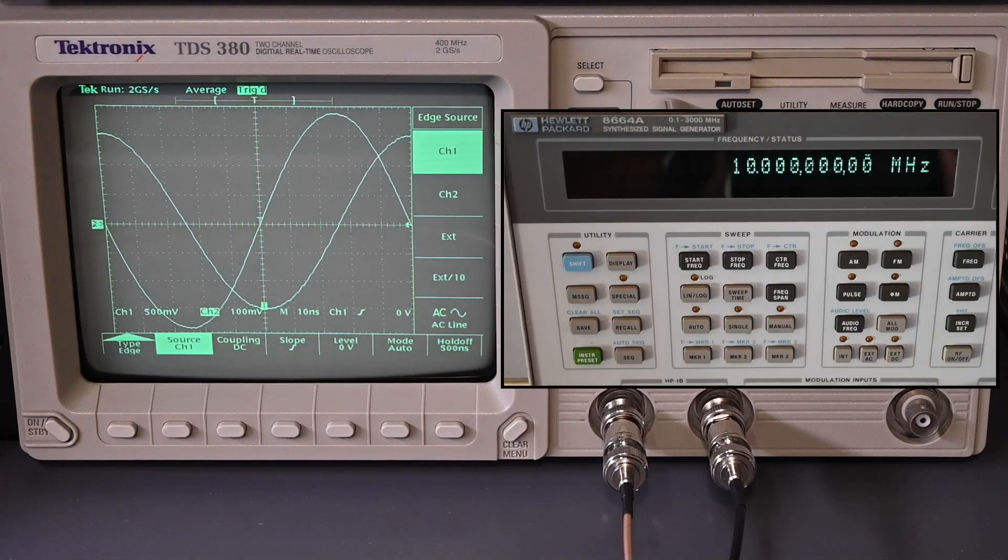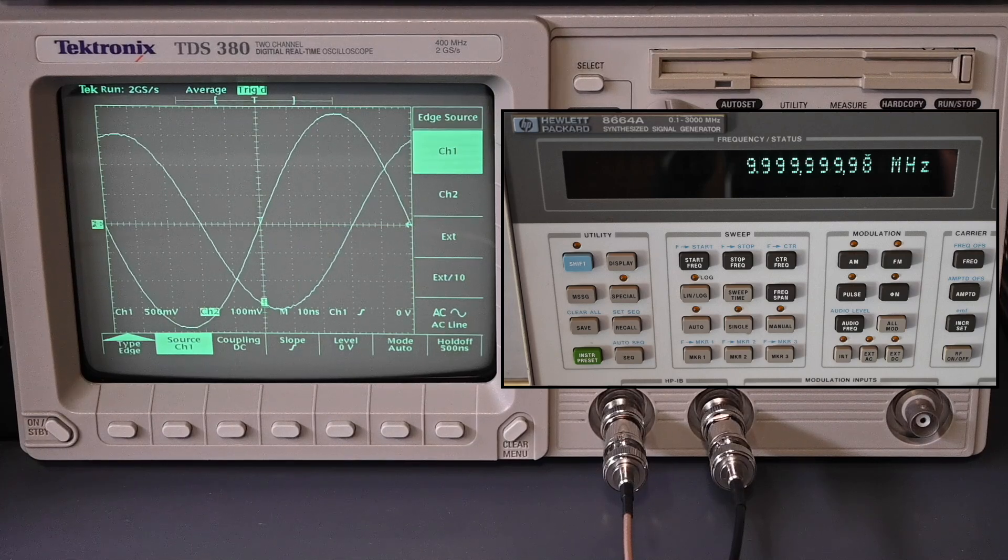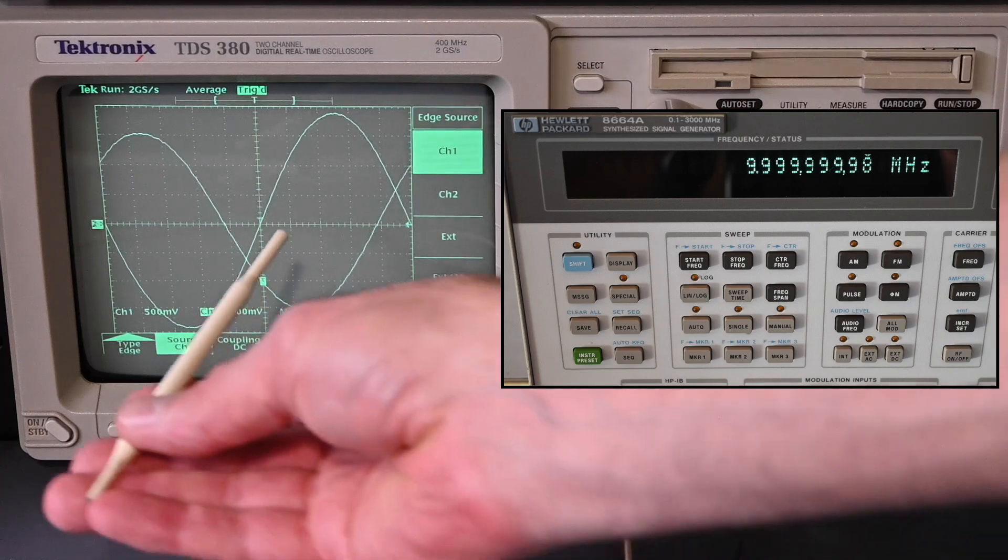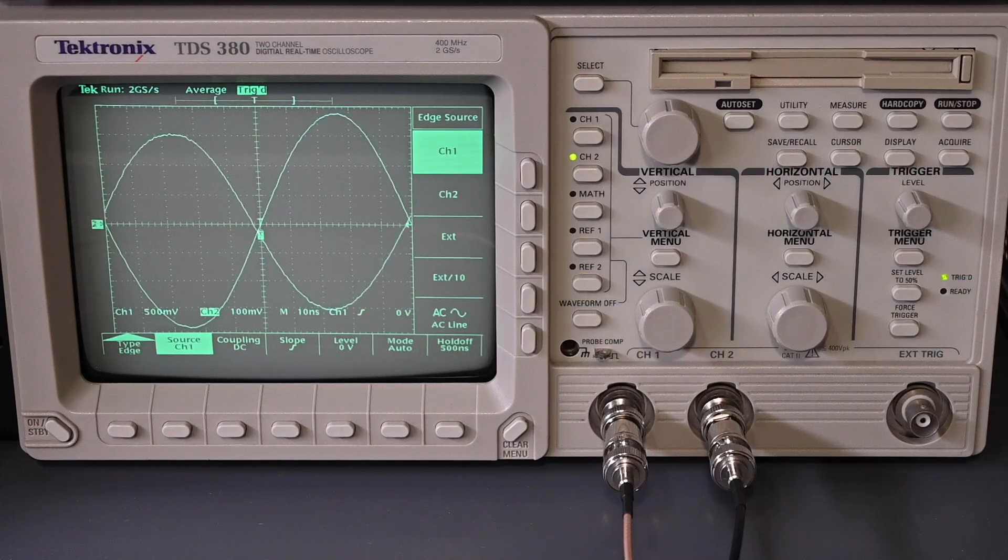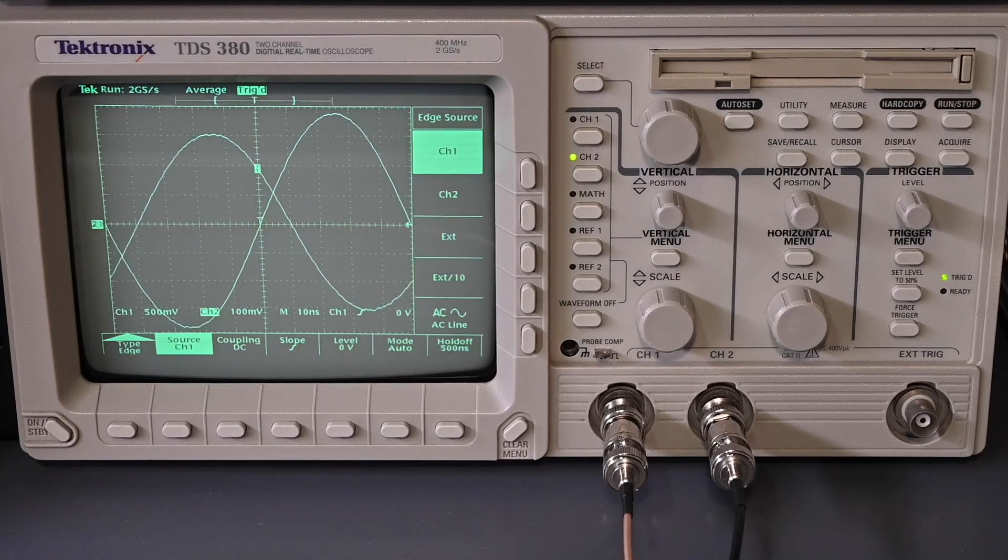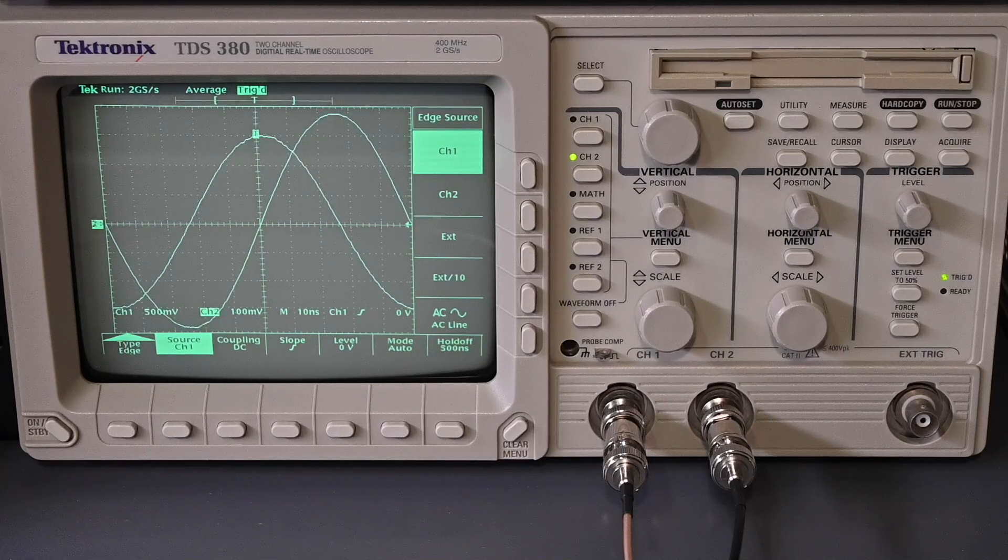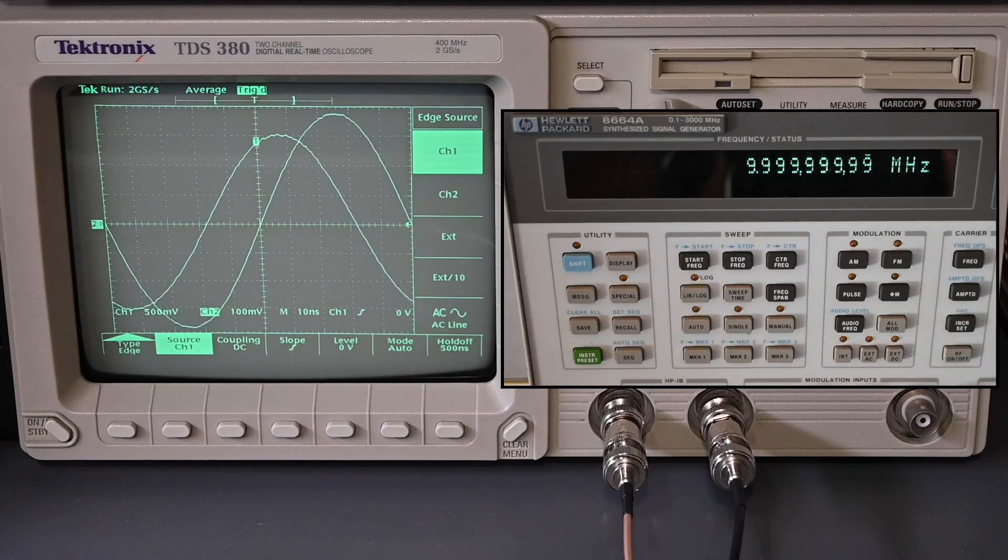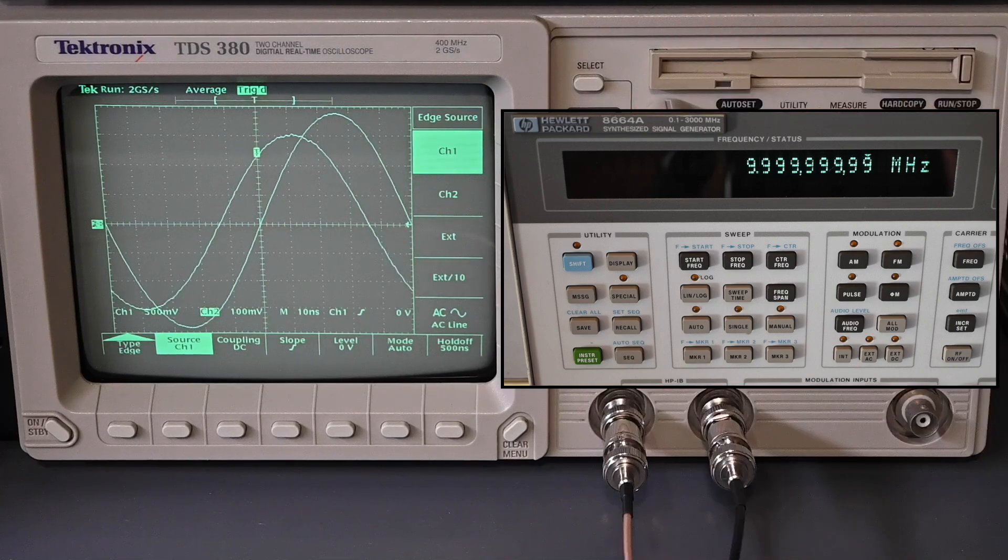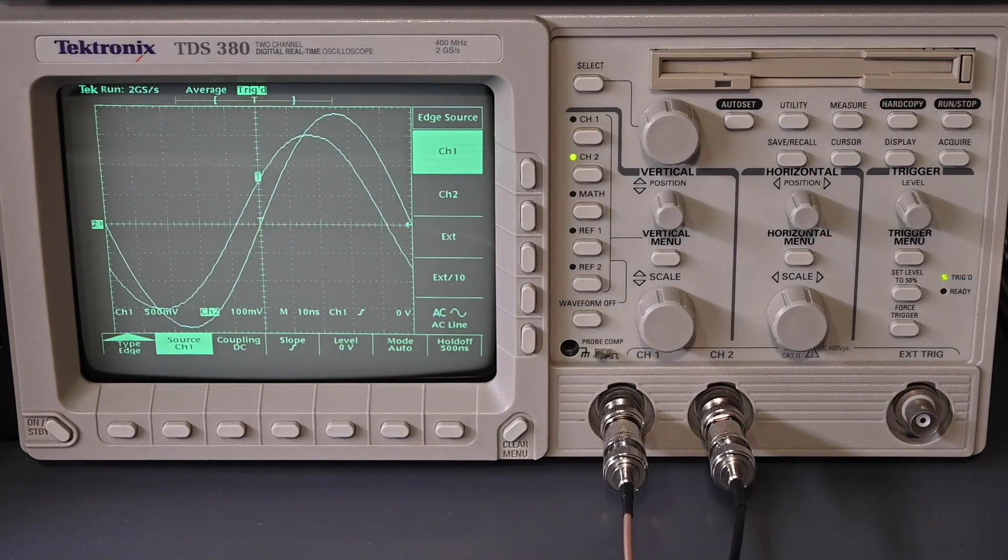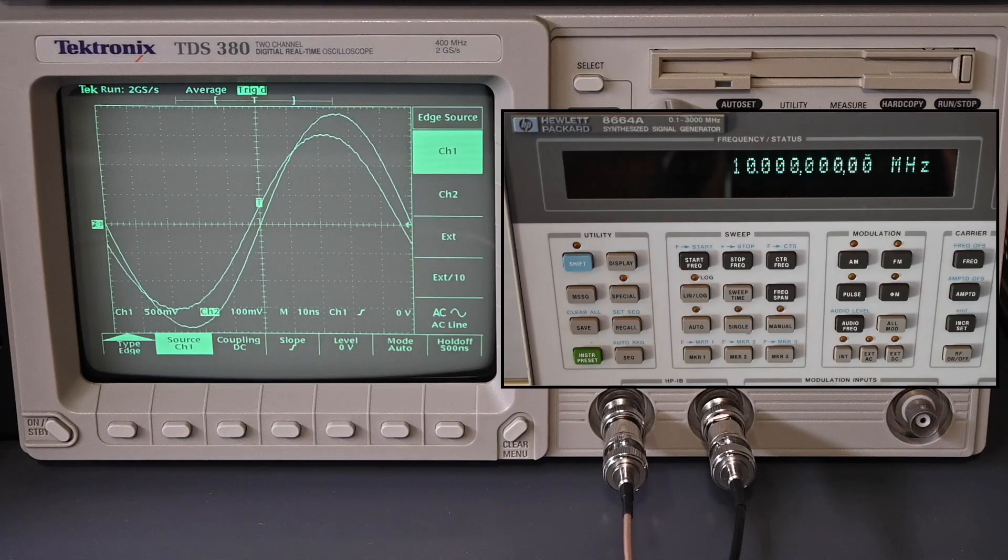But if I lower the frequency down, so I'll go 10 megahertz, I went down 20 millihertz below, and now you can see when it's lower in frequency, it's drifting the other way. And if I increase back up now by 10 millihertz, and excuse me, that went down by 10 millihertz. Let me go back up again here. Okay, so that's 10 megahertz, and then down by just 10 millihertz. So just drifting just a little bit, so it doesn't take much to make a visual change.